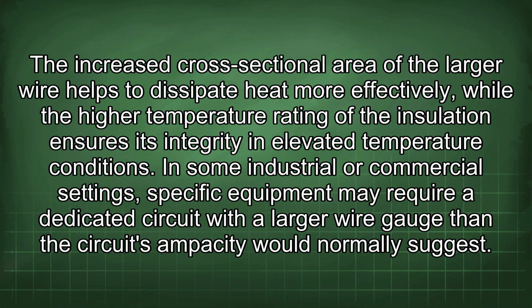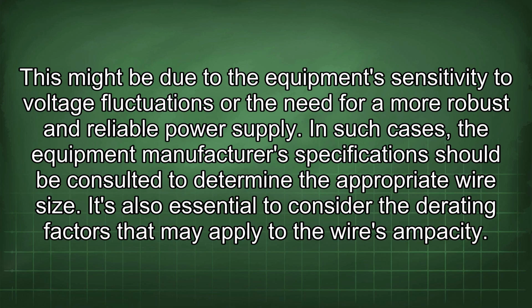In some industrial or commercial settings, specific equipment may require a dedicated circuit with a larger wire gauge than the circuit's ampacity would normally suggest. This might be due to the equipment's sensitivity to voltage fluctuations or the need for a more robust and reliable power supply. In such cases, the equipment manufacturer's specifications should be consulted to determine the appropriate wire size.